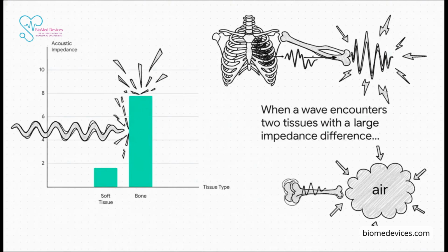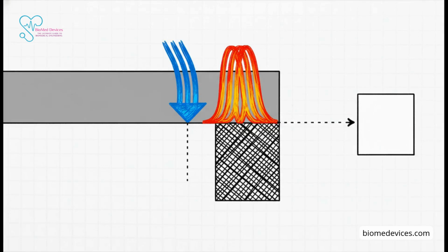But what happens when the pulse hits something totally different, like the boundary between some soft tissue and a solid piece of bone? Well, now, the jump in impedance is absolutely massive. The same thing happens, by the way, at the boundary between tissue and air. The difference is huge. This huge difference creates an incredibly powerful, strong echo. Almost all of the sound's energy just bounces right back to the probe. The machine sees this powerful return signal and paints a bright white pixel on the screen. This is why bone and things like gallstones show up as white.